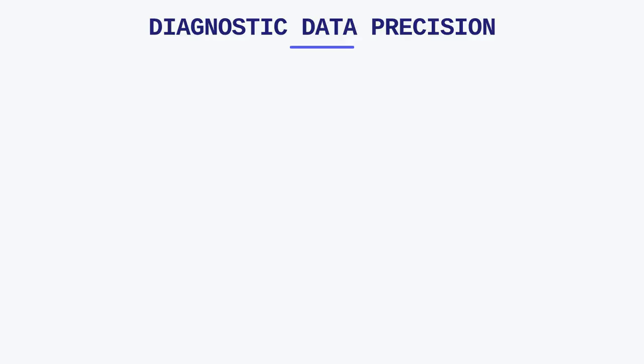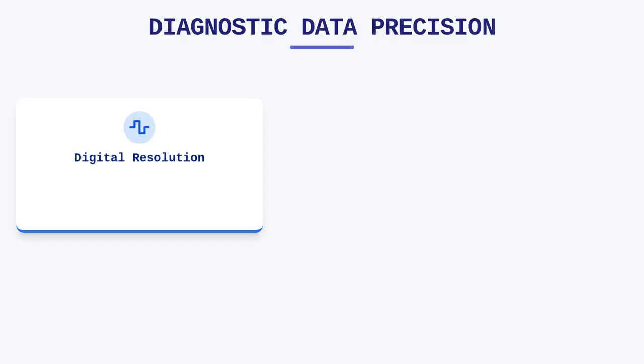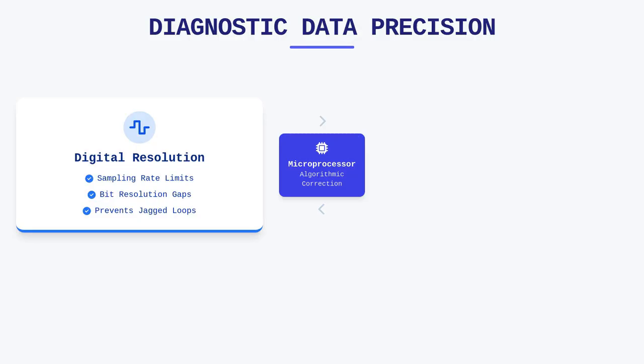The precision of your diagnostic data is ultimately limited by the system's digital resolution and sampling rate. If a device has a slow sampling rate or insufficient bits of resolution, the software cannot accurately capture the rapid peak flows seen at the very beginning of a healthy FVC maneuver, leading to a jagged or artificially smooth flow volume loop. Frequency response is another critical hardware parameter, as the transducer must be capable of reacting to the rapid onset of flow without significant mechanical lag or systemic overshoot.